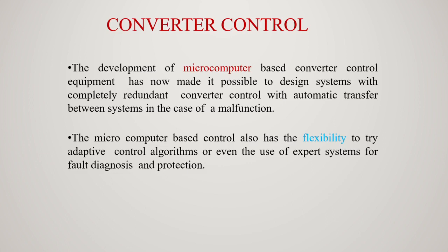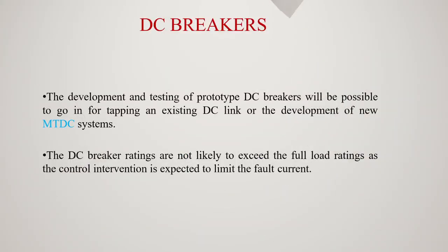The use of a mini simulator will make it feasible to check vital control and protection functions. Microcomputer based control also has the flexibility to try adaptive control algorithms or even the use of expert systems for fault diagnosis and protection. Control and protection will require measurements of direct current. Traditionally, direct current is measured using transducers of zero flux type based on magnetics, which are bulky and prone to problems during transients.